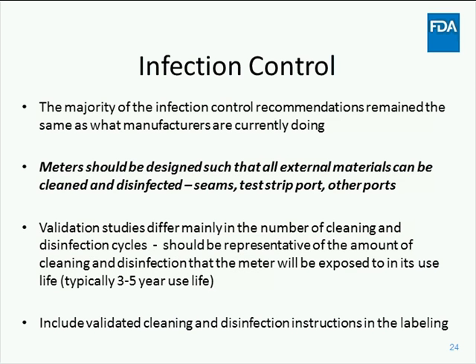One difference that I would like to highlight is the expectation that meters be designed such that all external materials can be cleaned and disinfected. This includes the test strip port, other ports, and any seams on the meter, etc. The validation studies in the two guidance documents are almost the same, differing mainly in the number of cleaning and disinfection cycles that represent the amount of cleaning and disinfection that the meter will be exposed to in its use life. Therefore, a meter used multiple times a day on multiple patients in a professional healthcare setting will need to be robust to many more cleaning and disinfection cycles as compared to a single patient over-the-counter meter. The validated cleaning and disinfection instructions should be included in the device labeling.